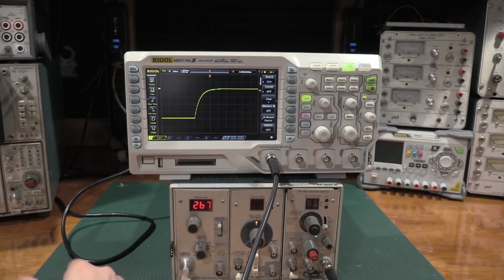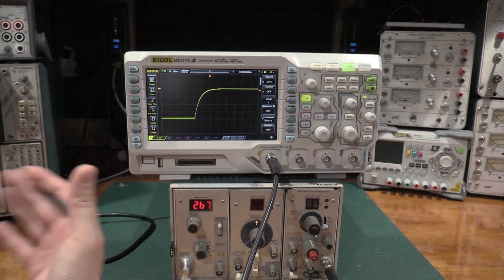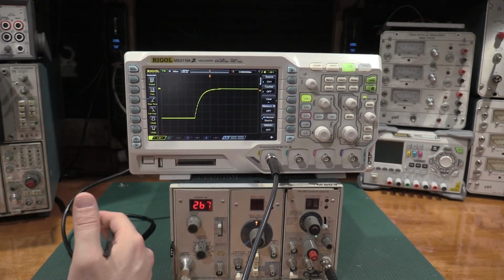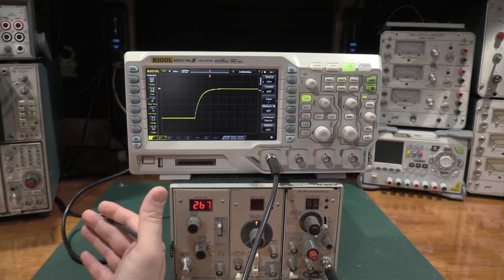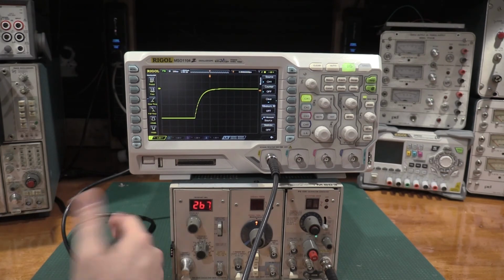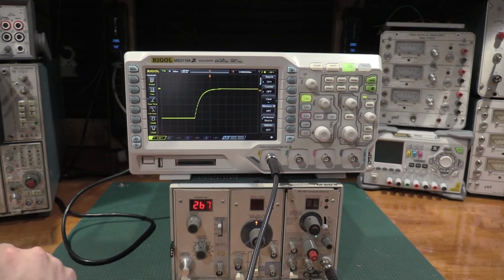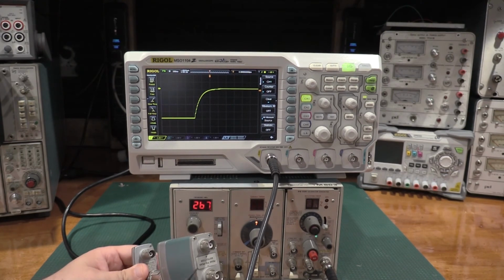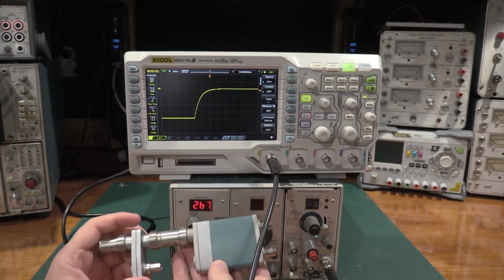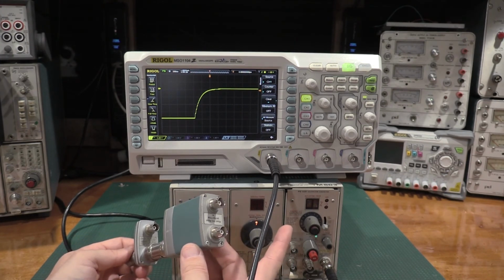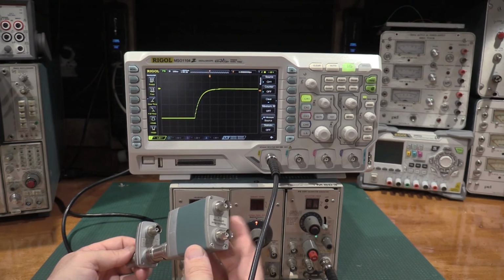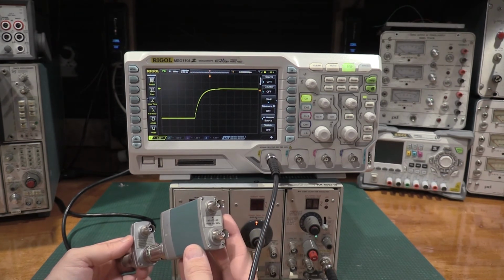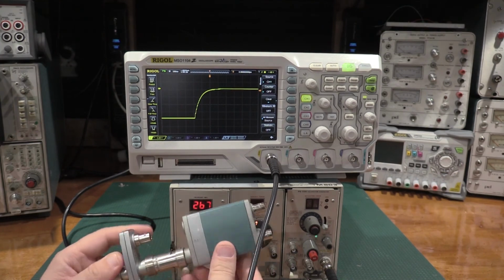Kick it up to the 485, some of the 7000s, where we're starting to get into the faster plugins, 200 megahertz for the 7826s, the 7819 at 500 megahertz. Got to go faster. Now we need the tunnel diode pulser and the high frequency leveled sine wave generator. Some keys to accuracy on these. On the SG503, one of the keys to accuracy is this peak-to-peak detector, which you saw me use at the end of the SG503 video. This allows the meter to say, yes, the leveling is happening. That's the important part. This unit right here is its basis of accuracy.